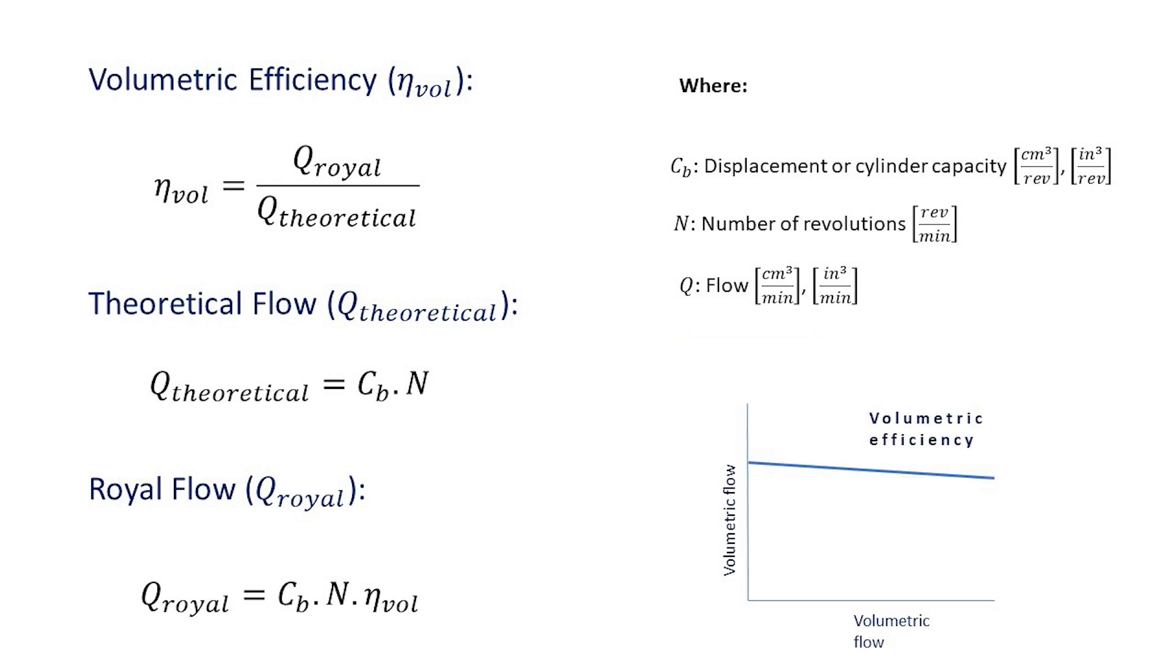In this graph it can be seen that the increase in pressure decreases the volumetric efficiency, since at higher pressure, the oil leaks in the pump are greater. If this parameter decreases, then the actual flow rate at the outlet will also be less.